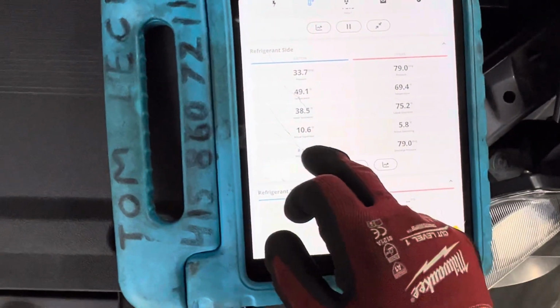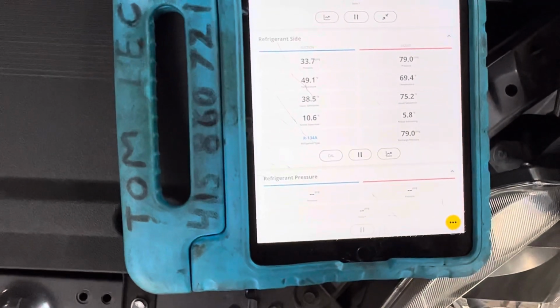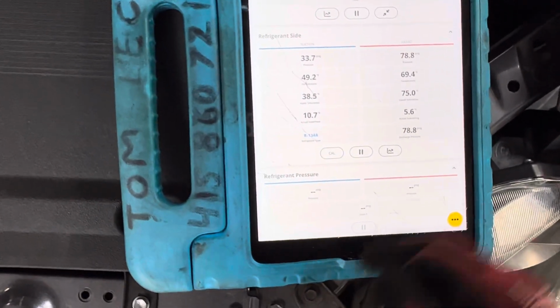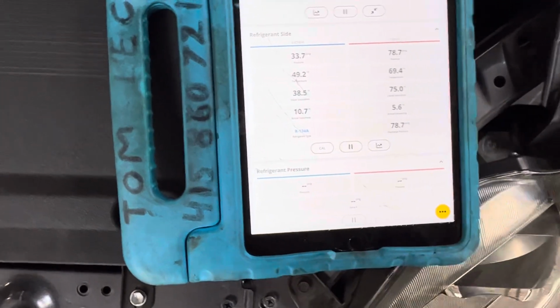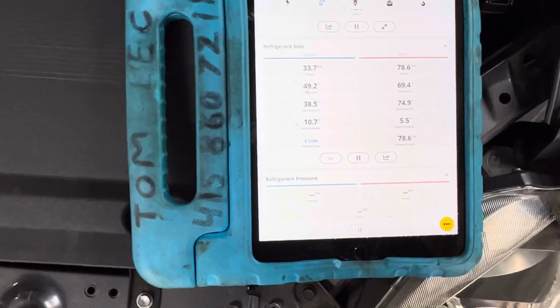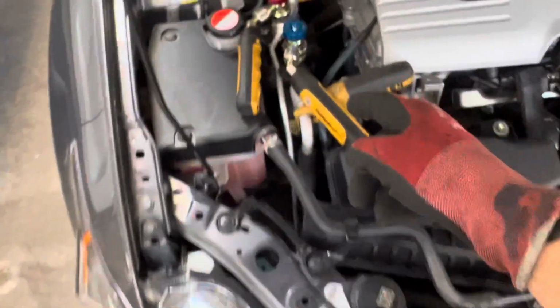What else do we got here? Let's go back. So our superheat on this one right now as it stands is 10 degrees superheat. Our subcooling, look at how low that subcooling is. Only 5 degrees. There's no TX or internal expansion.